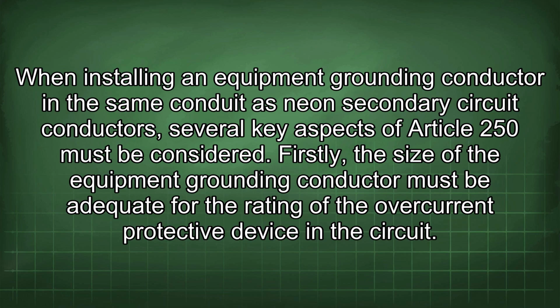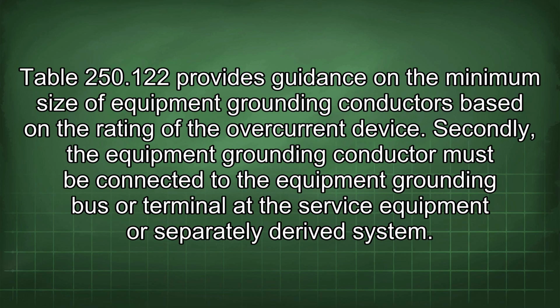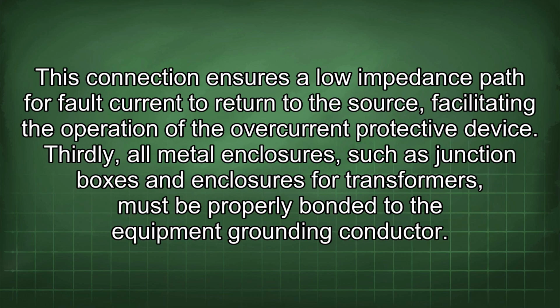When installing an equipment grounding conductor in the same conduit as neon secondary circuit conductors, several key aspects of Article 250 must be considered. Firstly, the size of the equipment grounding conductor must be adequate for the rating of the overcurrent protective device in the circuit. Table 250.122 provides guidance on the minimum size of equipment grounding conductors based on the rating of the overcurrent device. Secondly, the equipment grounding conductor must be connected to the equipment grounding bus or terminal at the service equipment or separately derived system. This connection ensures a low impedance path for fault current to return to the source, facilitating the operation of the overcurrent protective device.